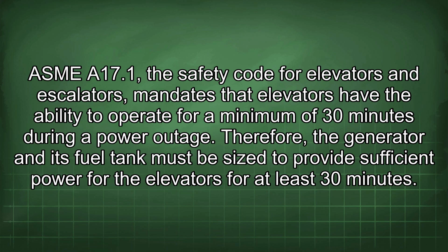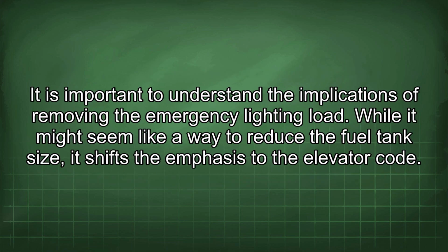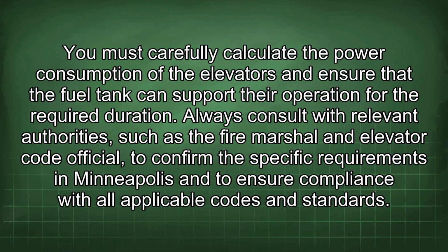30 minutes. It is important to understand the implications of removing the emergency lighting load. While it might seem like a way to reduce the fuel tank size, it shifts the emphasis to the elevator code. You must carefully calculate the power consumption of the elevators and ensure that the fuel tank can support their operation for the required duration.